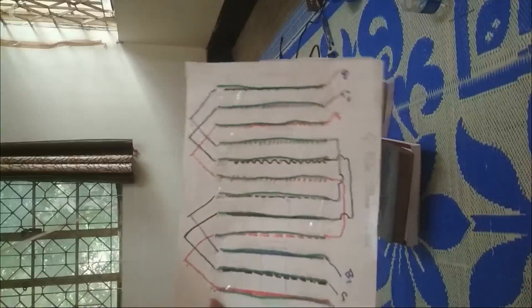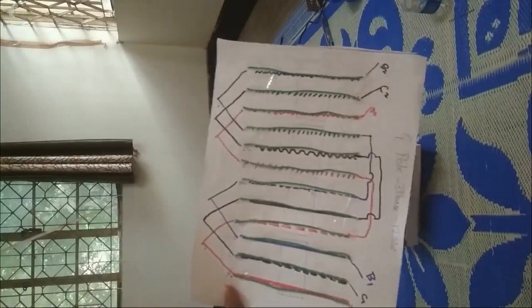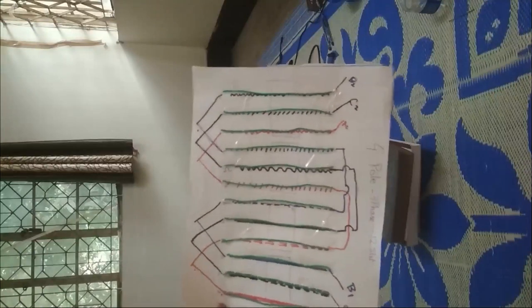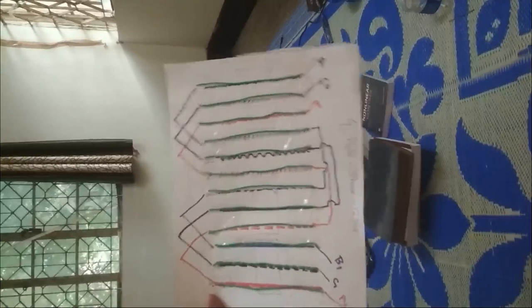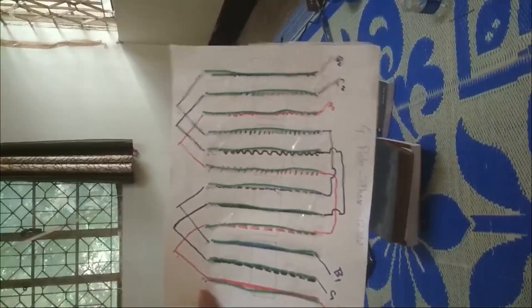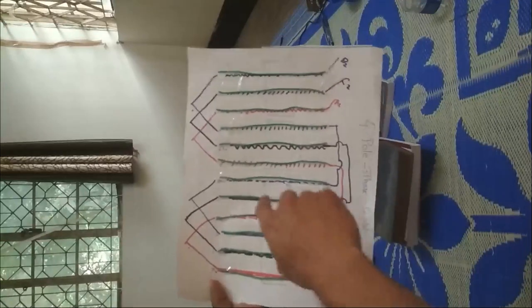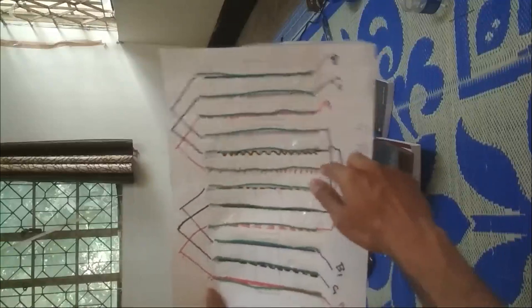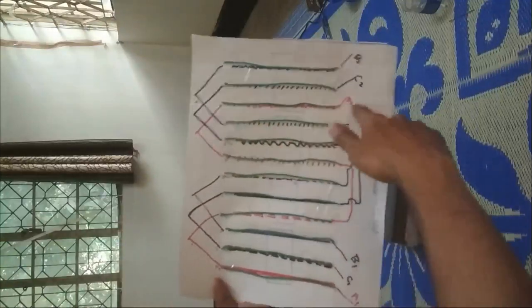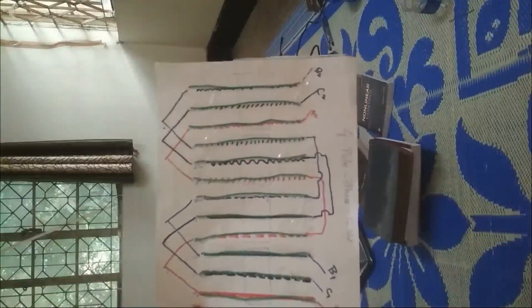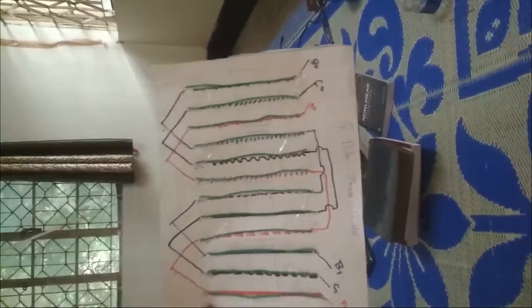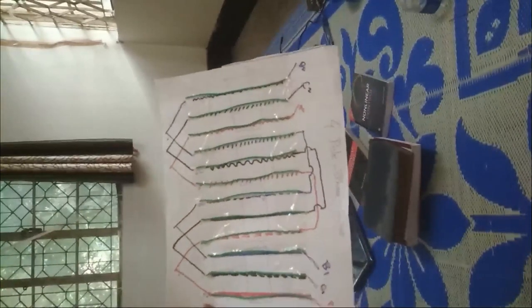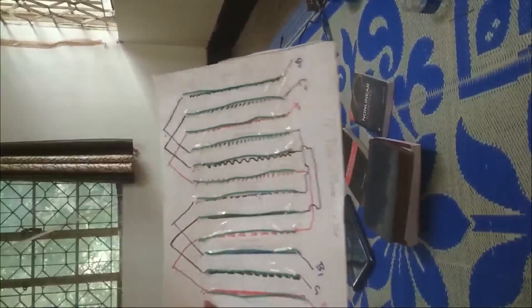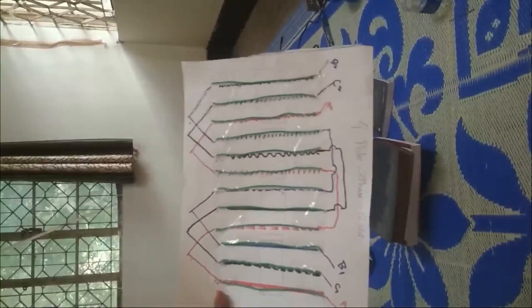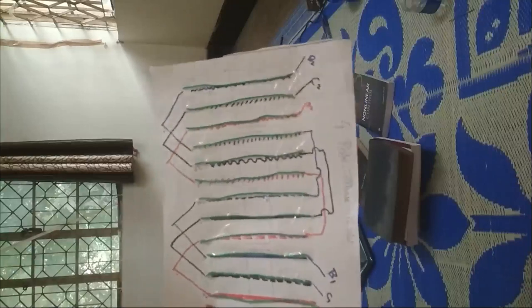Then what would be the next slot for A? That should be another three slots apart from the second A slot. The second A slot was 4, so the third A slot should be at 7, right? So this is the 7th A slot, and then another 3, the 10th. So the A phase winding is placed at 1, 4, 7, 10. Notice that all of them are 180 degrees apart from each other, and their total angular span is 180 into 4, that is 720 degrees, and that should be the case.